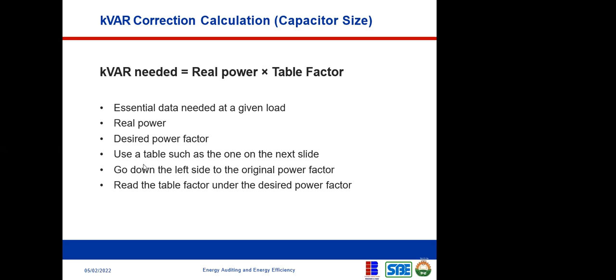Assuming you have 70, trace it horizontally up until the power factor that you desire. Assuming you desire 90% power factor, you look for where they coincide, and the value here is 0.536. Multiply this value with the real power, and once you do this, you have your kVAR.